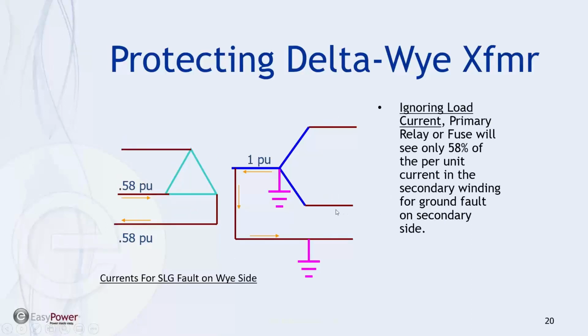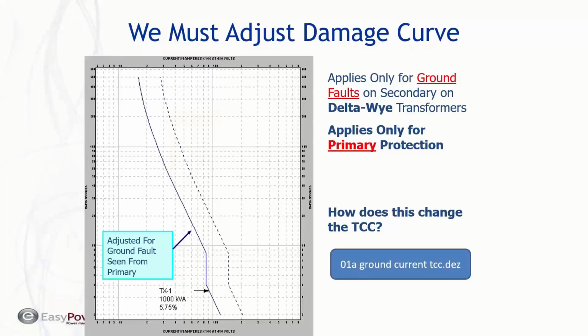However, if we have a single phase fault on the secondary, so we have a through single phase fault, and we're trying to protect or sense it on the primary side, then we can see that if we only have a 0.58 per unit current, that corresponds to a 1 per unit fault on the secondary side. So ignoring the load current, the primary relay or fuse will only see 58% of the per unit current that we've been monitoring for 3-phase faults. So what that means is we need to offset that damage curve by 58%, and this is what's referred to as an adjusted ground fault seen from the primary. So let me see if I can illustrate that. I've actually saved that plot.